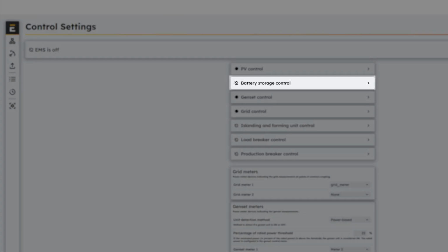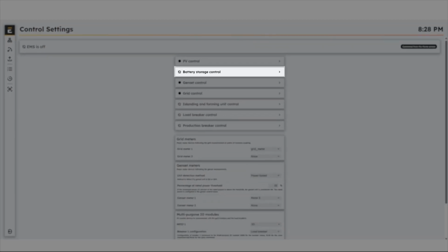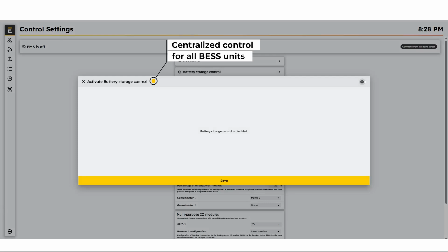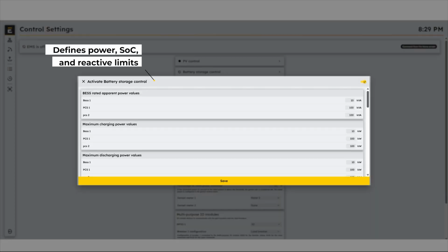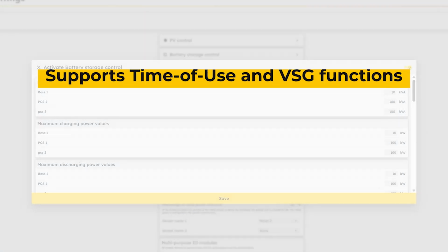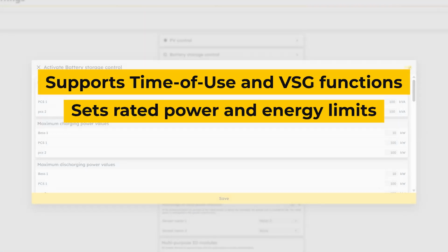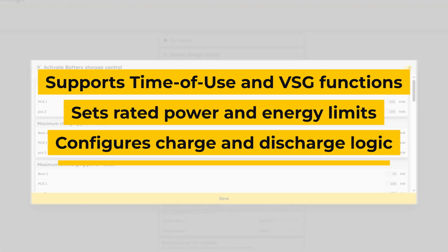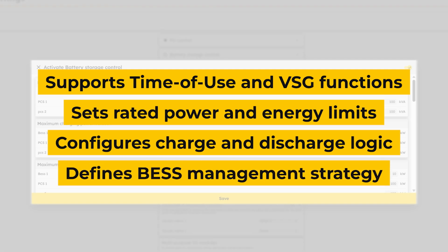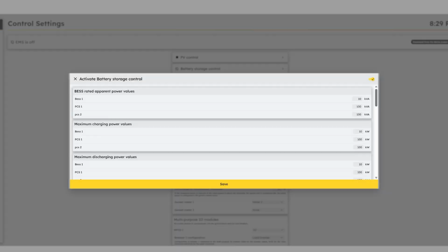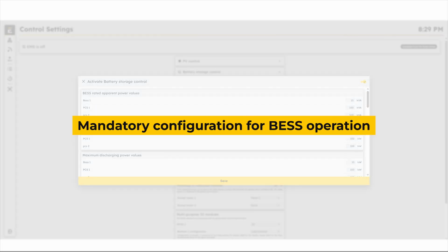The Battery Control tab defines how the EMS manages your energy storage system, setting rated power and energy limits, defining charge and discharge logic, and coordinating advanced functions like time of use or VSG operation. In this section, you must define the rated power, capacity, and SOC limits for each battery and PCS unit. These settings are mandatory for proper EMS operation.